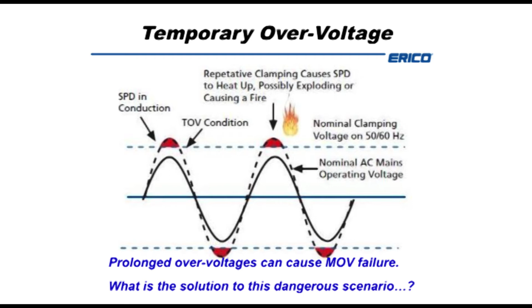So that's a short duration, higher frequency event. Here's the two circuits we're talking about. The older one is on the left. There's a bank of metal oxide varistors in parallel with some thermal fusing connected in series. The one on the right is our transient discriminating technology. The switch you can see above the bank of MOVs is a TD switch, a frequency dependent switch.